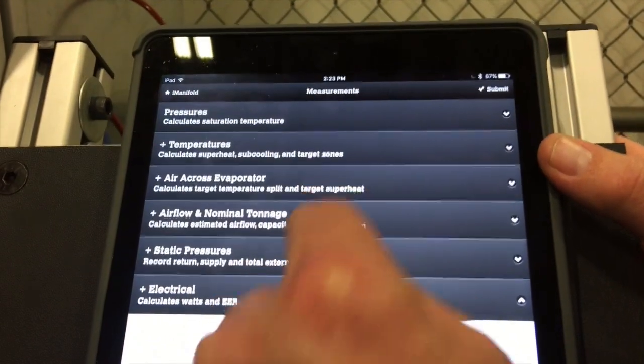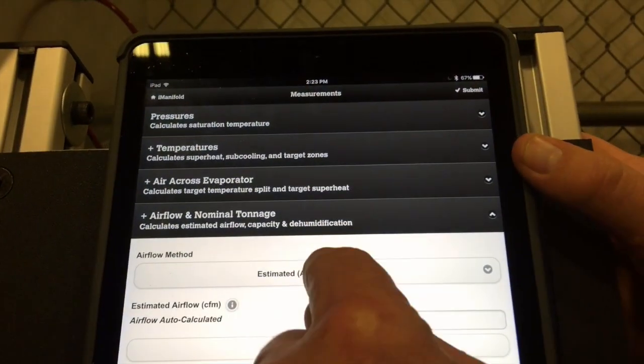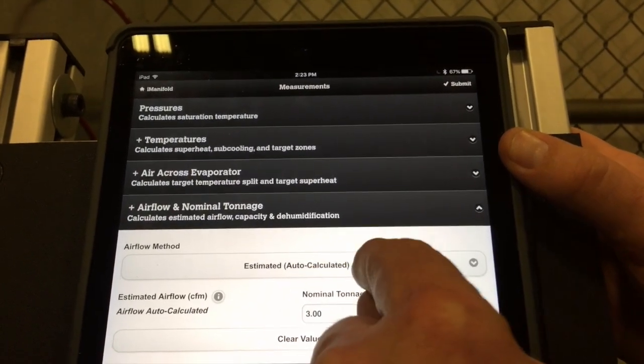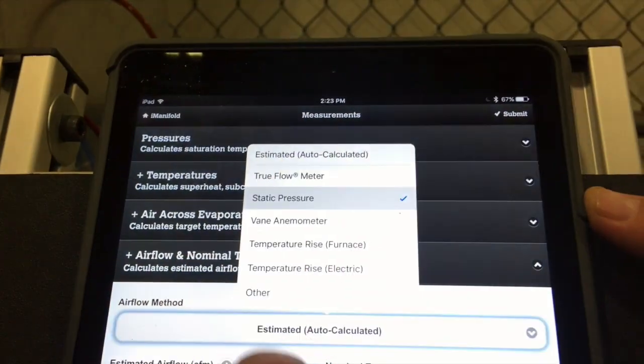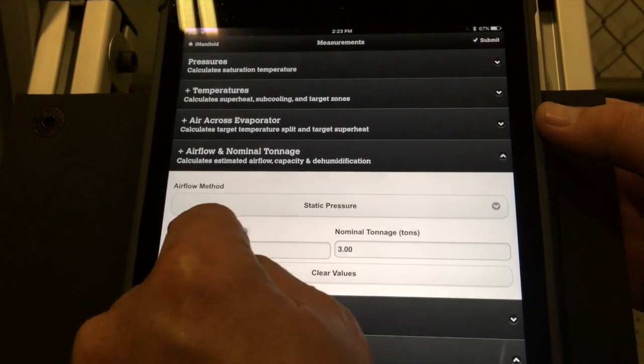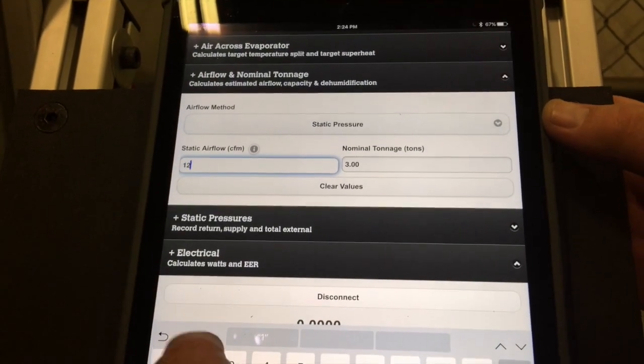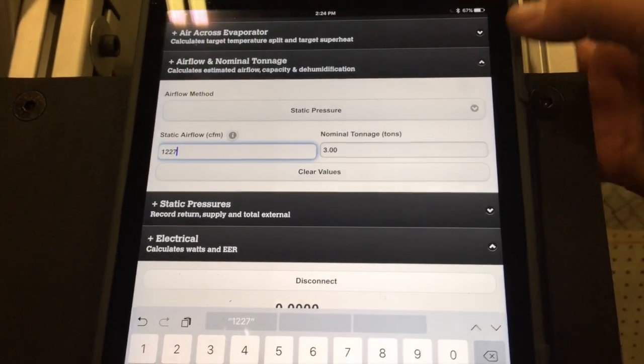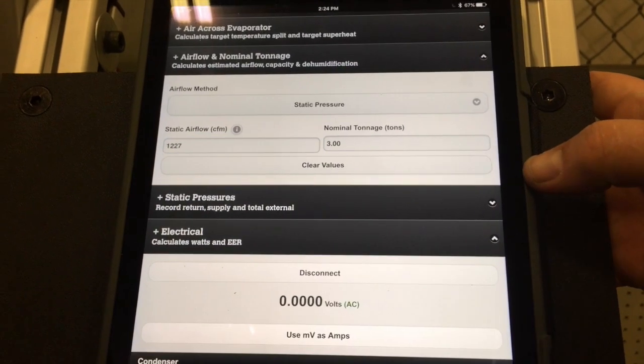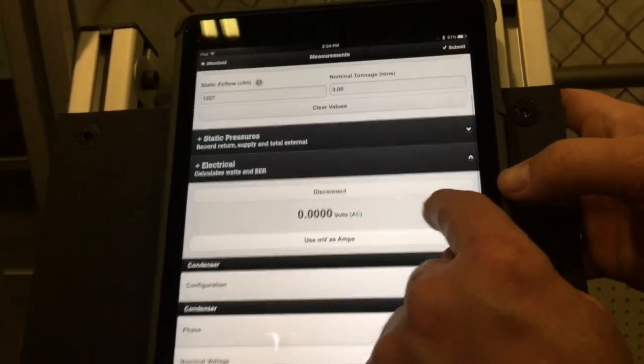And we're going to go here to airflow nominal tonnage. Instead of our estimated calculated, we're going to use static pressure. It's going to ask us for a CFM, 1227 CFM. And now we'll go ahead and we'll measure our voltage.